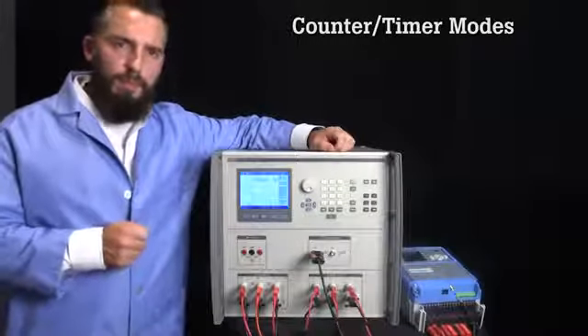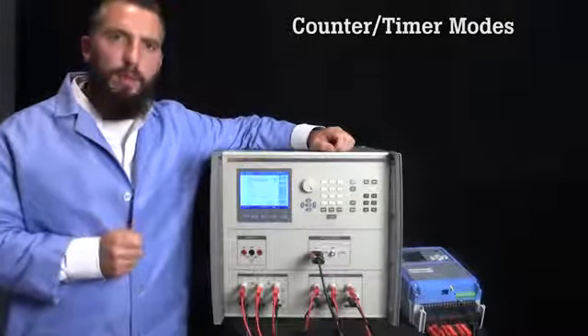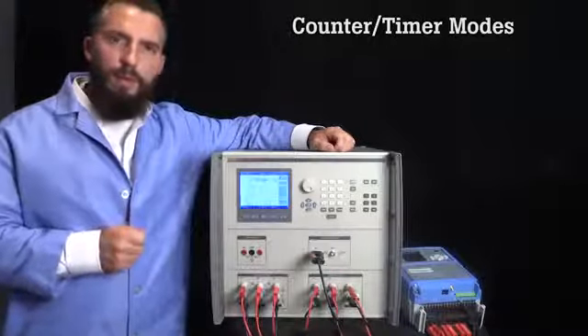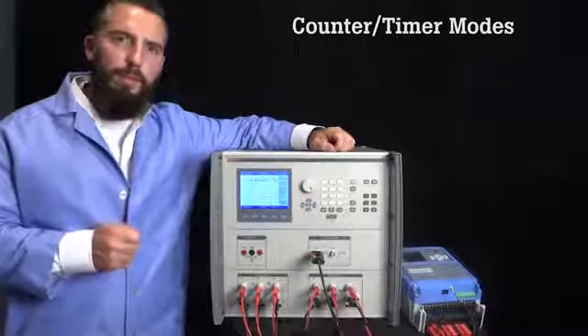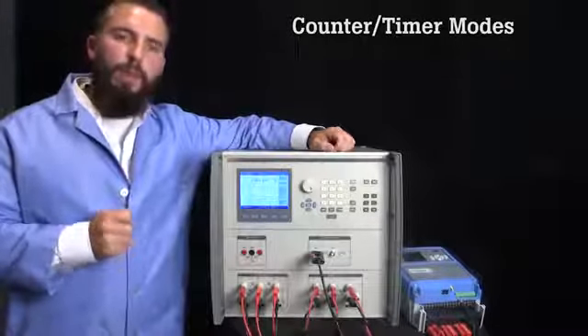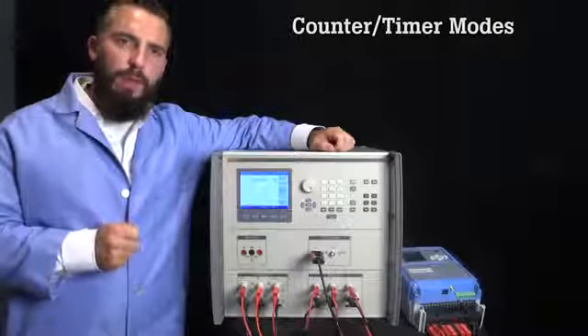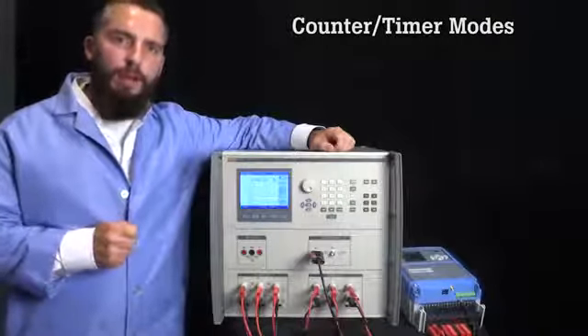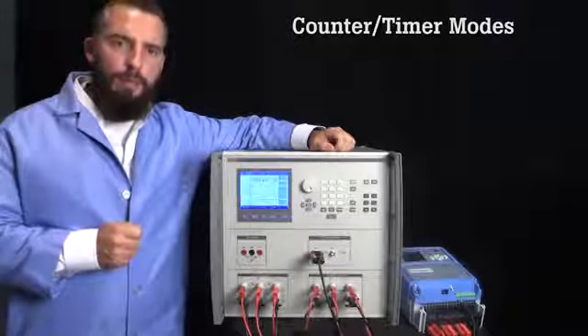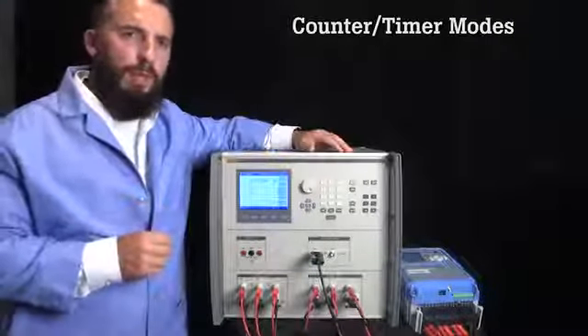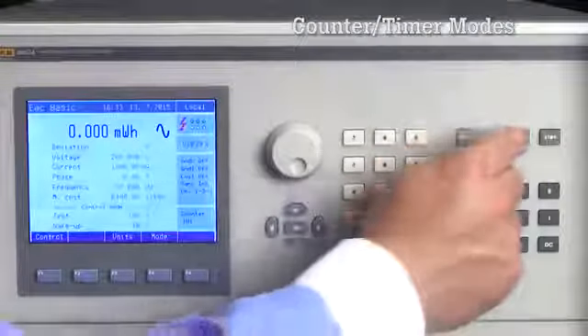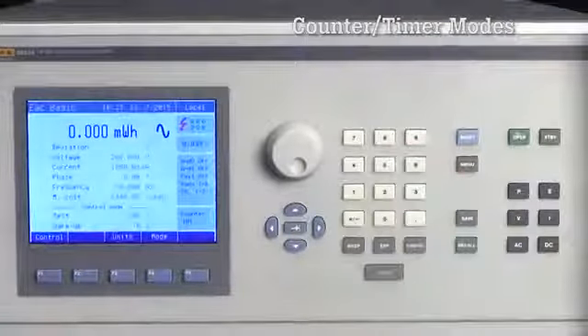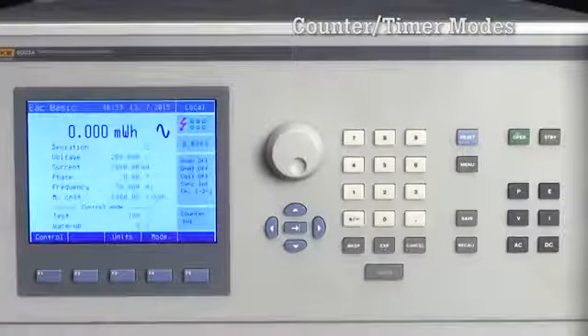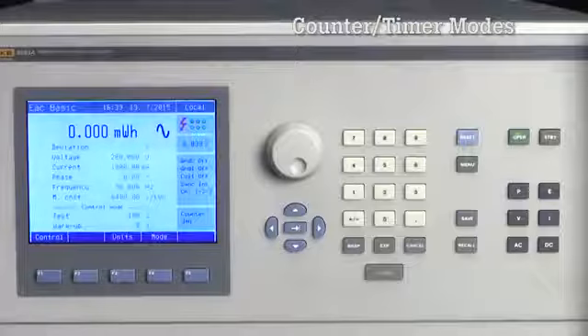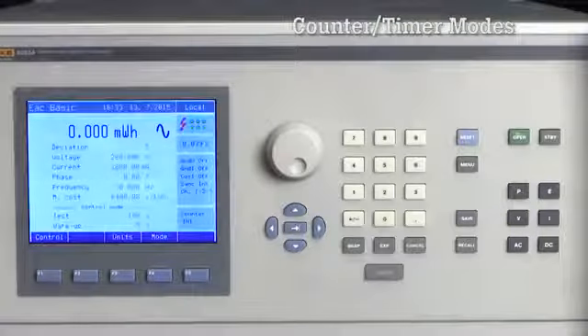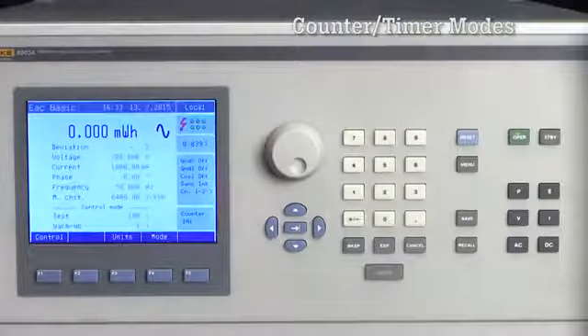I will set the test to receive 10 pulses as a warm-up and run for 100 pulses. In other words, the 6003A will apply power to the UUT, wait for 10 pulses from the UUT, then test until another 100 pulses have been counted. I will now push the operate key to start the test. The 6003A starts to count energy pulses. After it has received the amount of warm-up pulses prescribed, the test will run for the amount of pulses set in the test.